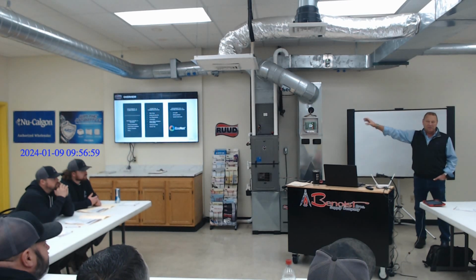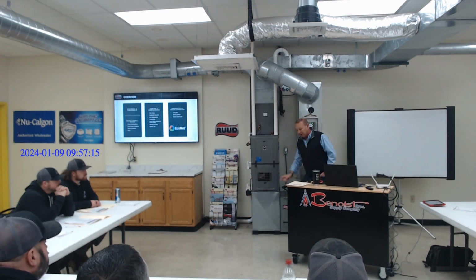We just kept replacing modules, right, because they were under warranty, about every 2 or 3 years. Well, now these motors are communicating, and they're going to start folding back and throwing errors, especially when communicating, okay? So the basis of this is to understand our CFMs and our static pressure. I've got a couple of short videos I can show you on how the motors actually work, or we can do one live.